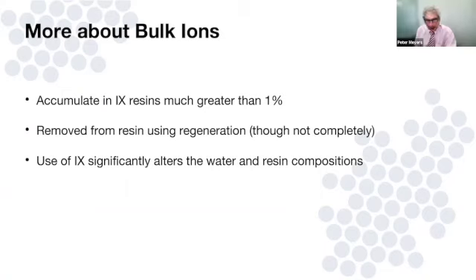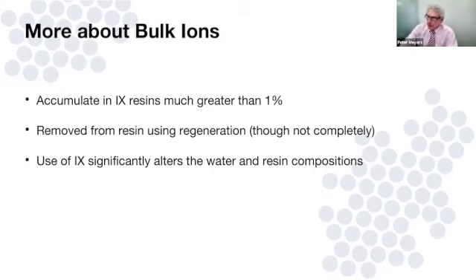There are some fundamental differences between bulk ions and trace ions with respect to ion exchange resin. Bulk ions accumulate in the resin to much greater than one percent, and because throughputs tend to be short — we're loading the resin up rather quickly — most bulk ion removals are associated with a regeneration process. The resin is cycled between exhaustion and regeneration hundreds or even thousands of times, making the regeneration cycle every bit as important as the exhaustion cycle.